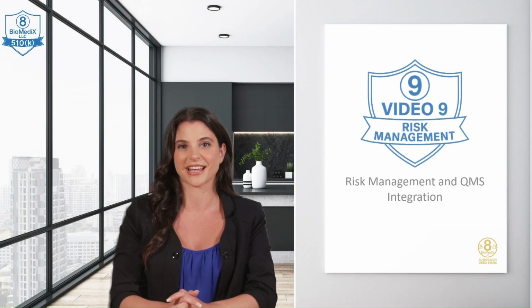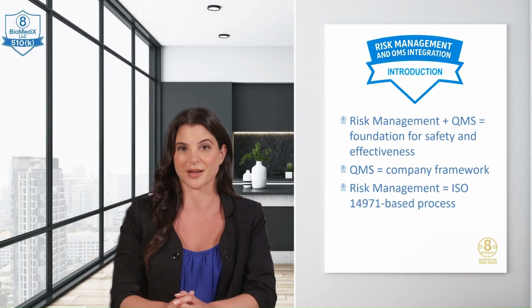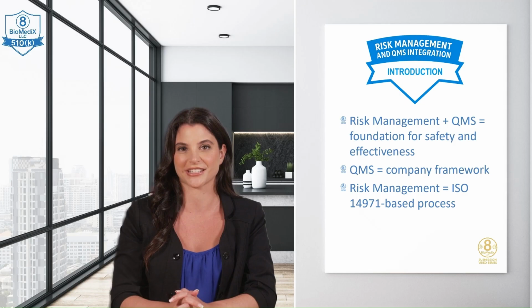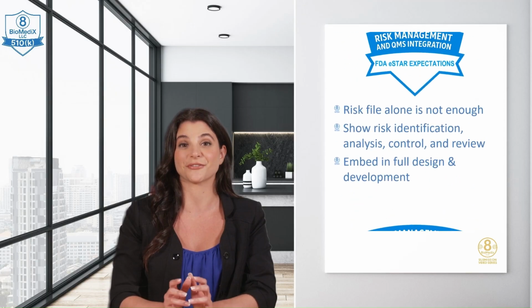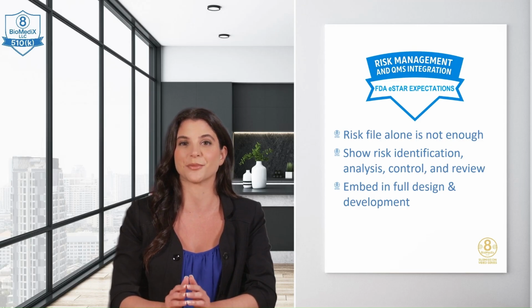Welcome back to our 510(k) submission series. In this video, we'll explore two interconnected pillars of medical device development and regulatory compliance: risk management and quality management system, QMS, integration. While your QMS is your company's overarching framework, a fully integrated risk management process, primarily guided by ISO 14971, is what truly underpins the safety and effectiveness claims in your 510(k) submission. The FDA's eSTAR platform heavily relies on your diligent application of risk management principles.